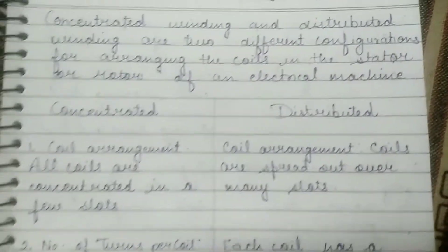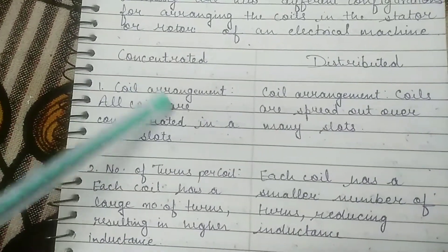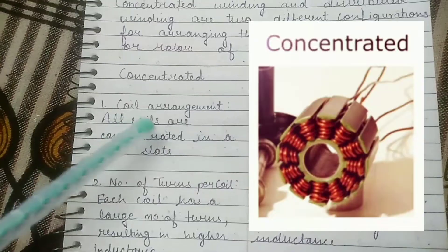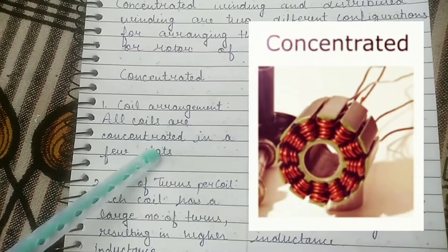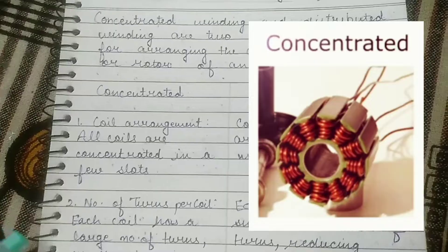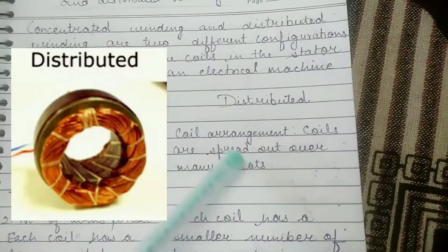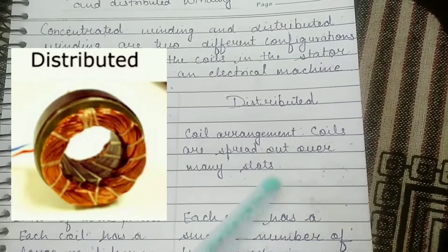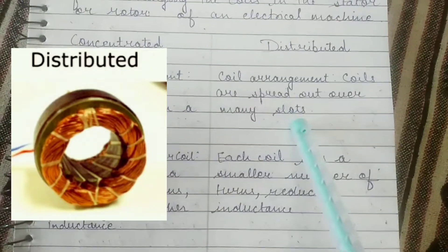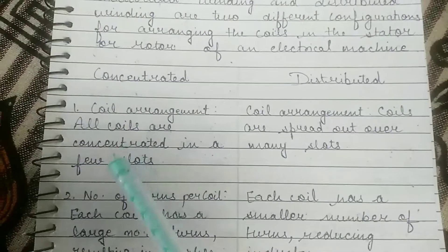The first difference is coil arrangement. In concentrated winding, all coils are concentrated in a few slots, leading to a simpler layout. But in distributed winding, coils are spread out over many slots, resulting in a more complex layout where coils are interconnected to form a distributed winding pattern.